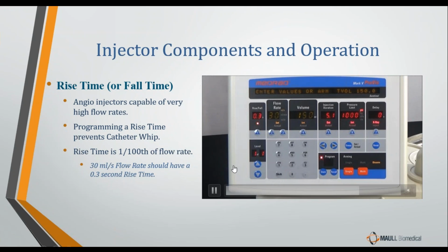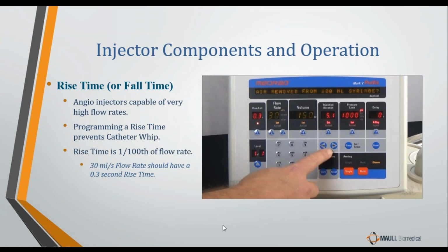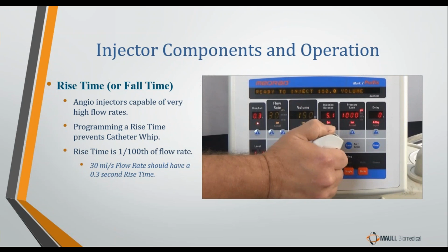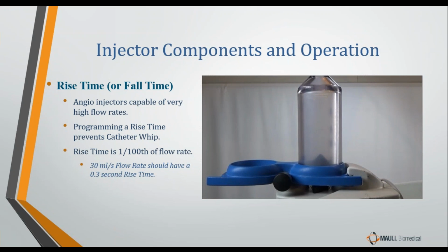Now what that's going to do is, pause this for a second. Now instead of, when we start the injection, going from 0 straight immediately to 30 milliliter per second flow rate, we will take 0.3 seconds to go from 0 to our selected flow rate. So by slowly rising up to our selected flow rate, that diminishes or eliminates catheter whip. And we perform the injection, and we see our syringe slowly build up to full speed.